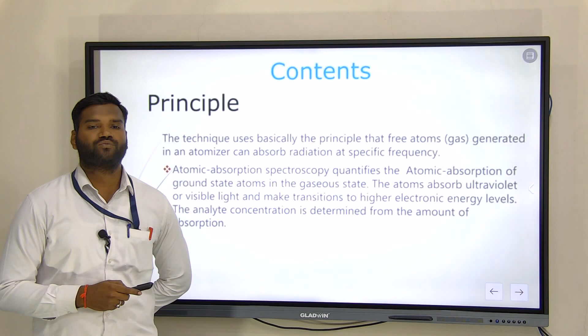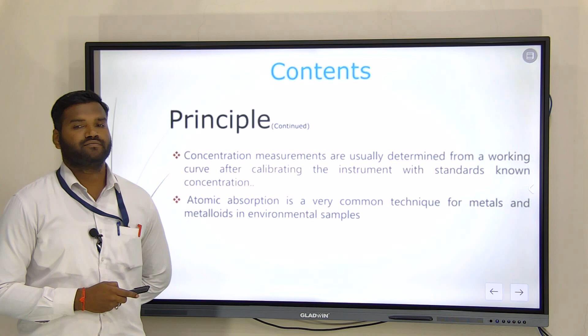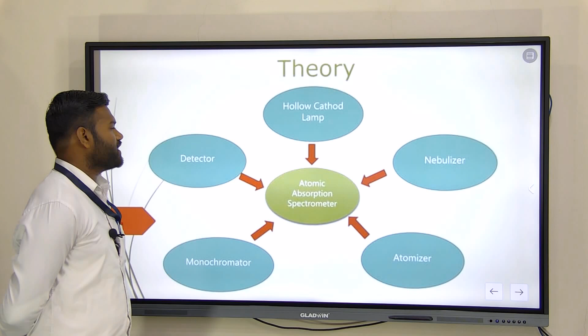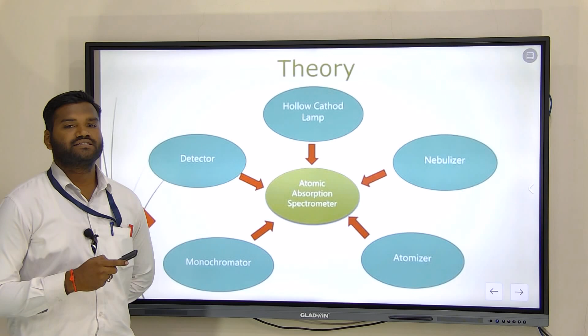Concentration measurements are usually determined from a working curve, after calibrating the instrument with standards of known concentration. Atomic absorption is a very common technique for metals and metalloids in environmental samples. Generally, the atomic absorption spectrometer is based on a hollow cathode lamp, then nebulizer, then atomizer, then monochromator, and lastly the detector.